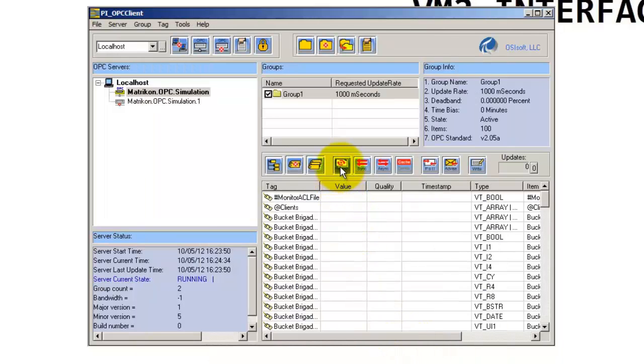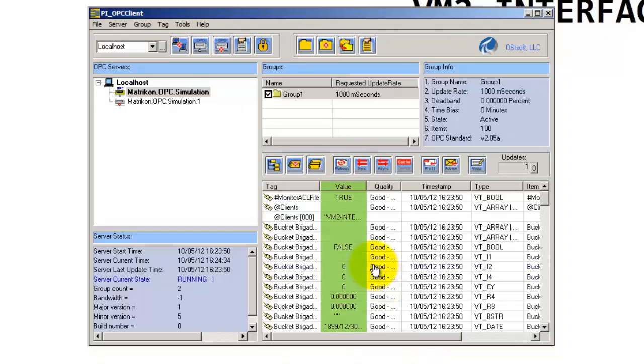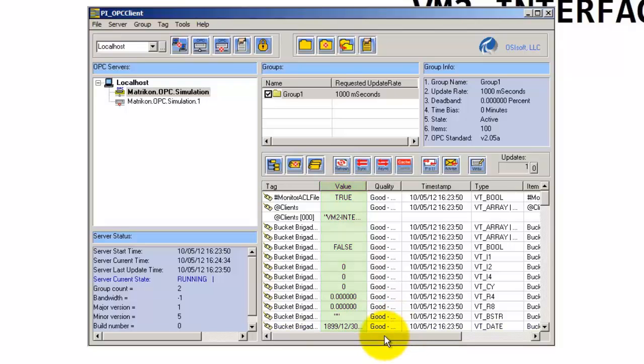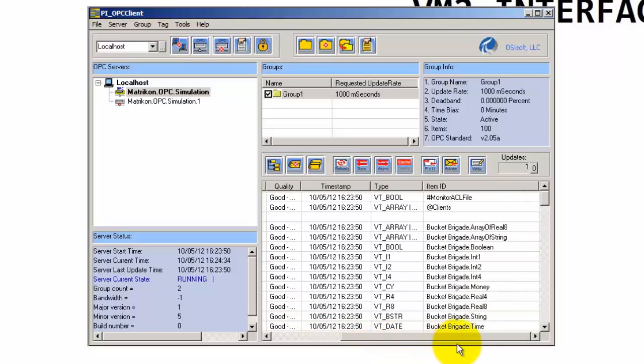These are all the tags. If we hit Refresh, we can see the values we're getting for these specific tags. This confirms that we are connected and can receive these values. One thing that's going to be particularly important for us later is the last column, Item ID. This is what we're going to be using to specify the instrument tag when we create points on the PI server node.